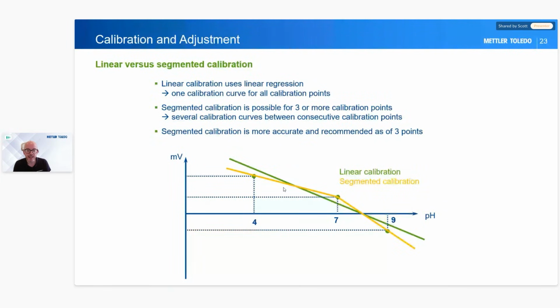What this does is it gives us a really more accurate calculation of what's happening with the real behavior. Because yet again, in the theoretical behavior, we say, oh, it's just one big straight line. But in reality, it never works like that. And therefore, we have this calculation. And you can use that in some meters. So yeah, again, the Mettler meters for the 7 direct and 9 focus do what we call a segmented calibration. And some of the 5+ series as well do segmented.